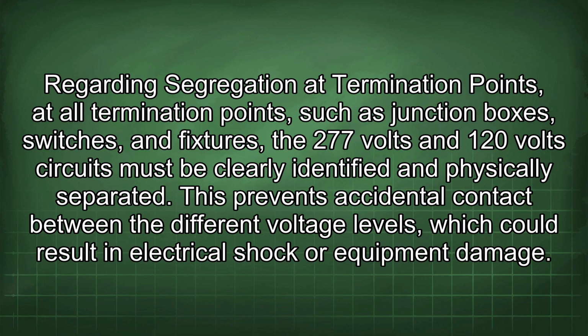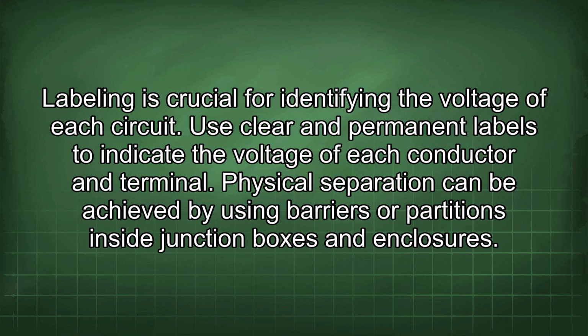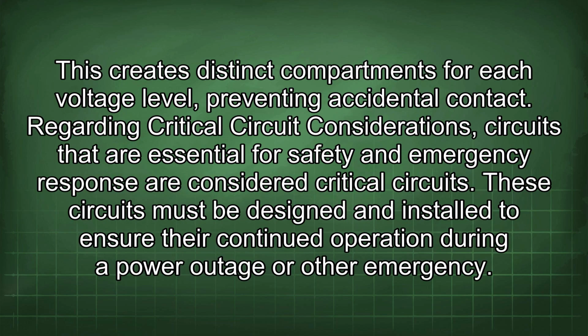Regarding segregation at termination points, at all termination points such as junction boxes, switches, and fixtures, the 277 volt and 120 volt circuits must be clearly identified and physically separated. This prevents accidental contact between the different voltage levels, which could result in electrical shock or equipment damage. Labeling is crucial for identifying the voltage of each circuit. Use clear and permanent labels to indicate the voltage of each conductor and terminal. Physical separation can be achieved by using barriers or partitions inside junction boxes and enclosures. This creates distinct compartments for each voltage level, preventing accidental contact.